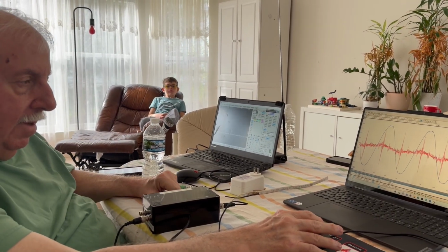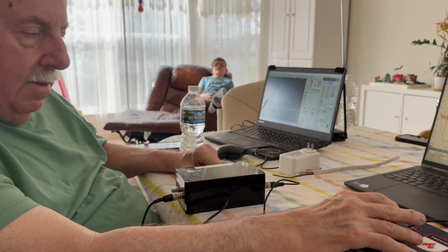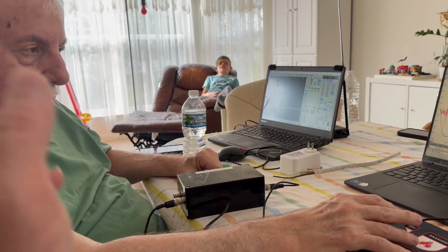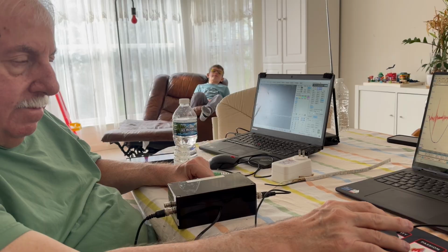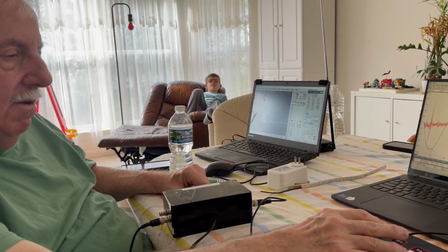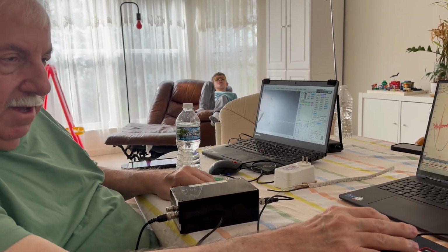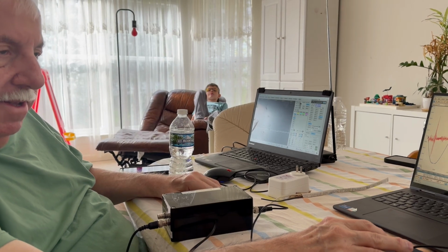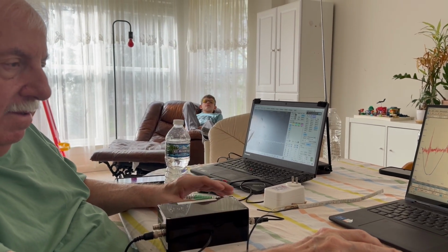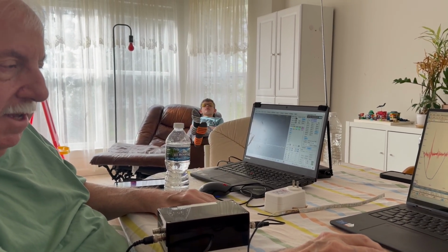And then what about ground current, Bill? Could that get into the ground current and be picked up even from houses further away, from all the neutral? Ground current's everywhere, right. The neutral's not big enough, that's just the way the grid is made. So the neutral's not big enough to go back like it is in Russia and other areas around the world. It uses the ground.